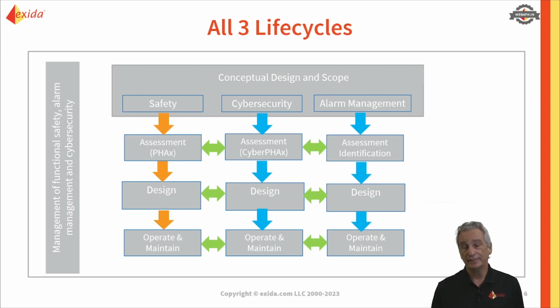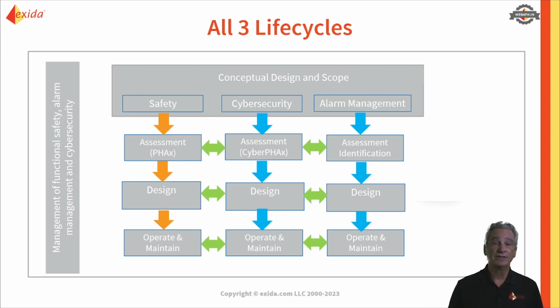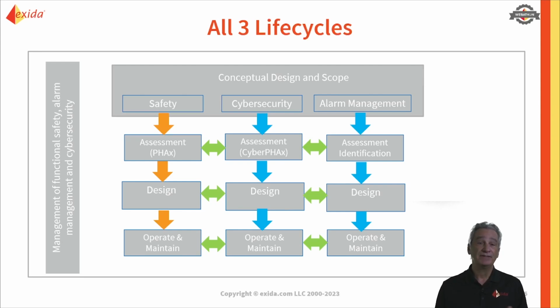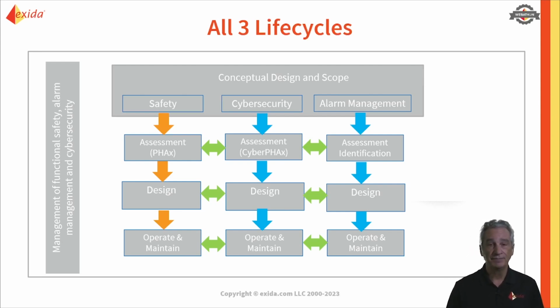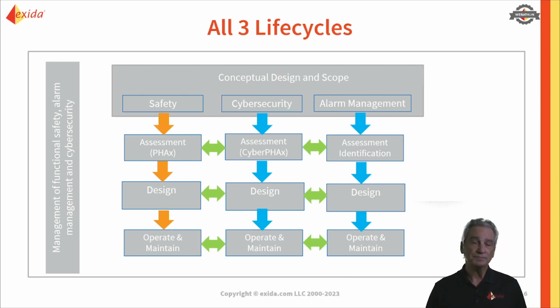In fact, there's an ISA technical report group committee, the TR84.09, and they came up with an approach that's very similar to the safety, in that we have a cyber security management system, we have a cyber security management plan for how we're going to implement cyber security, and we do cyber security assessments and cyber security audits in the same way as we would do for safety. So this is the same approach. It's just recommended that we follow that. So that ties us in with, again, the functional safety side of things.